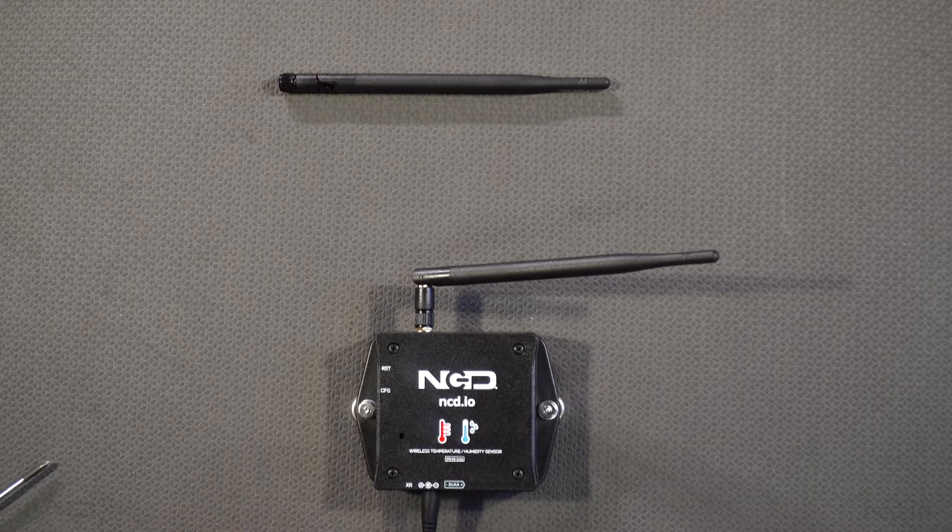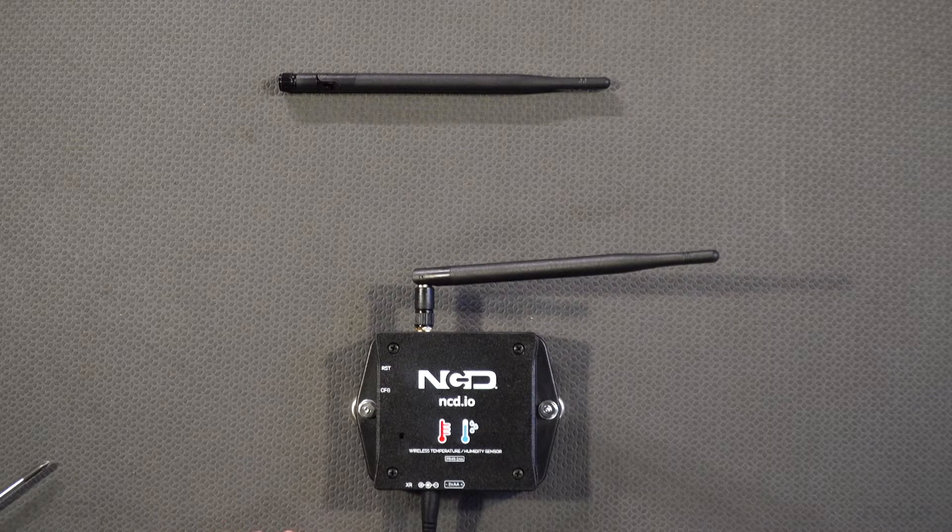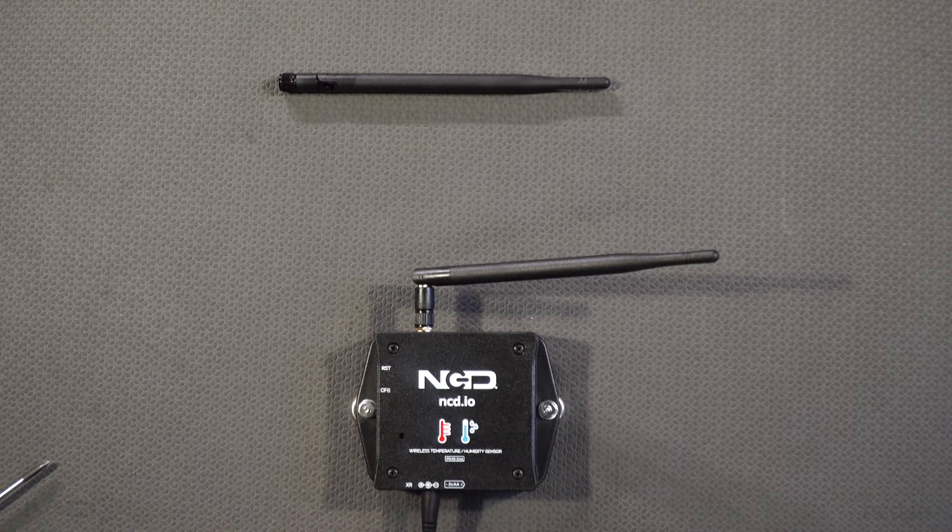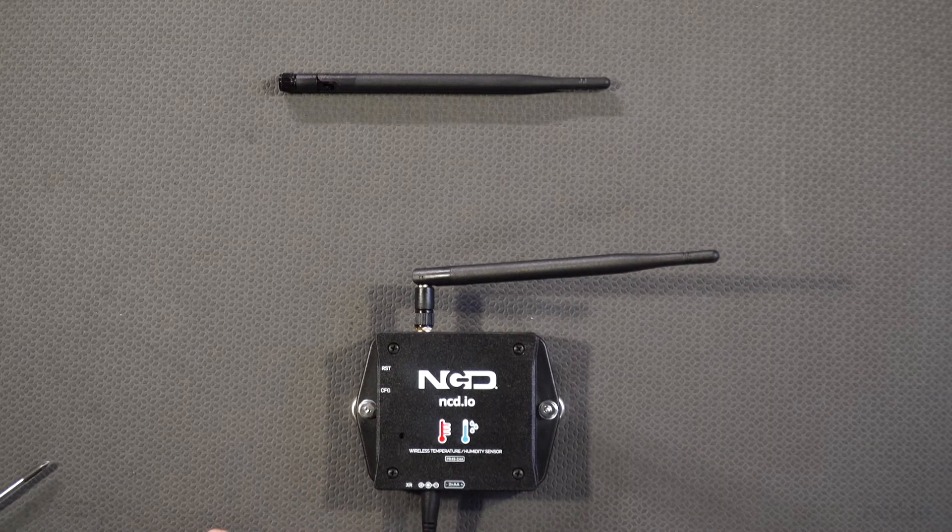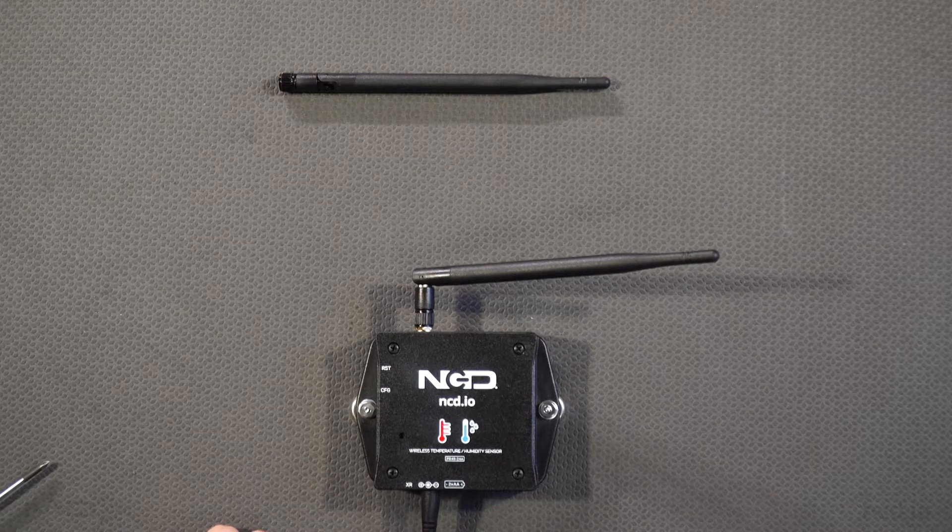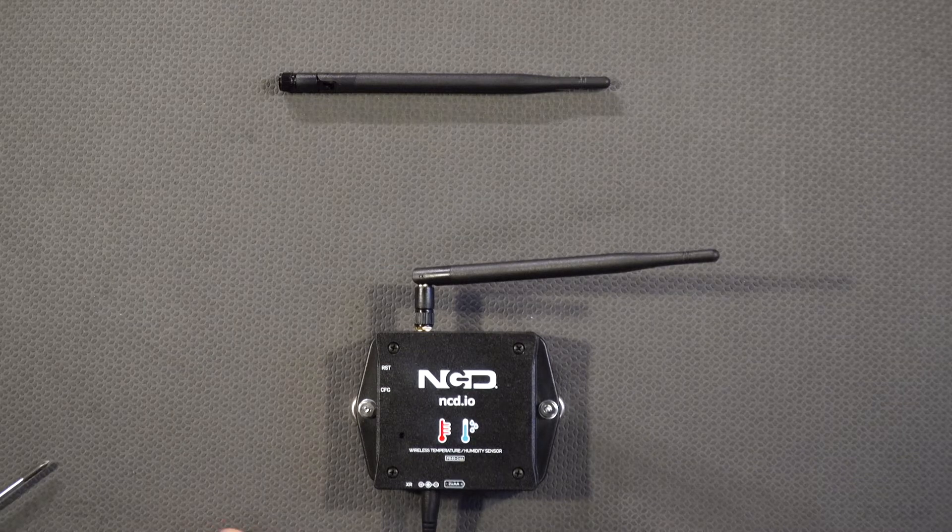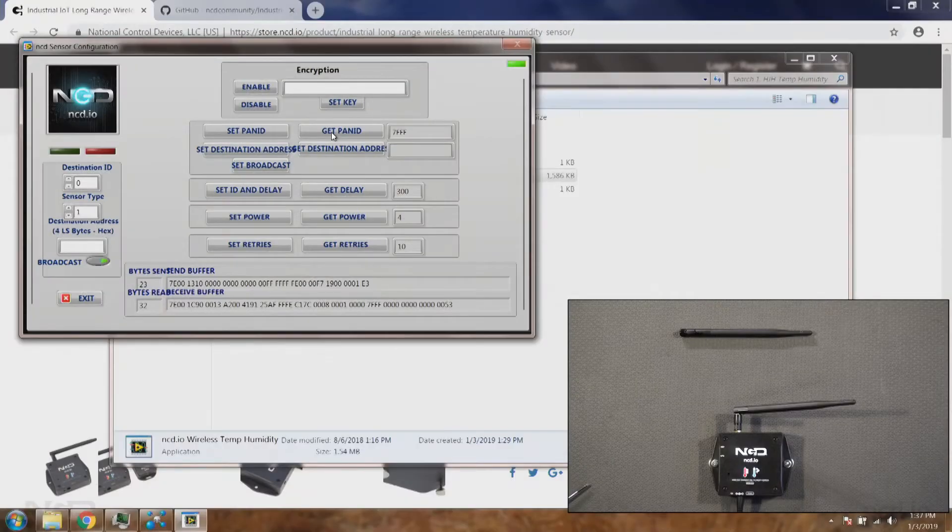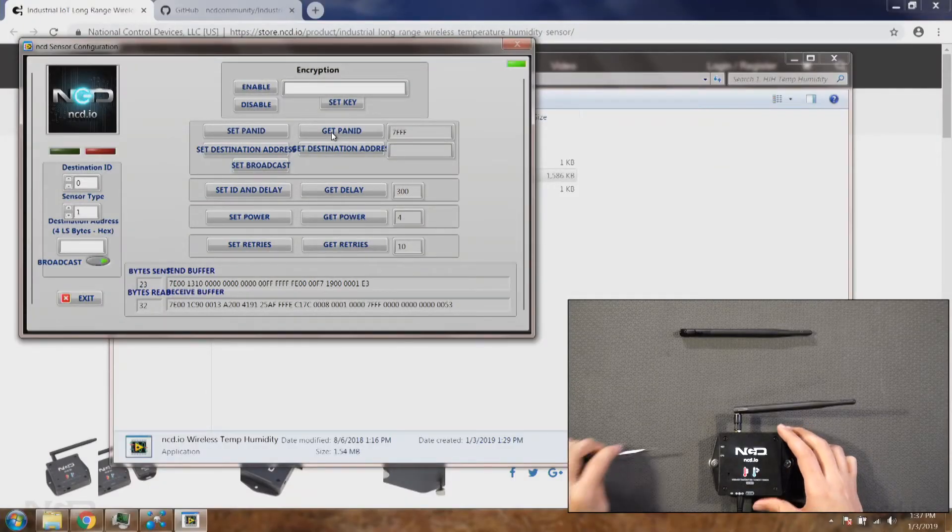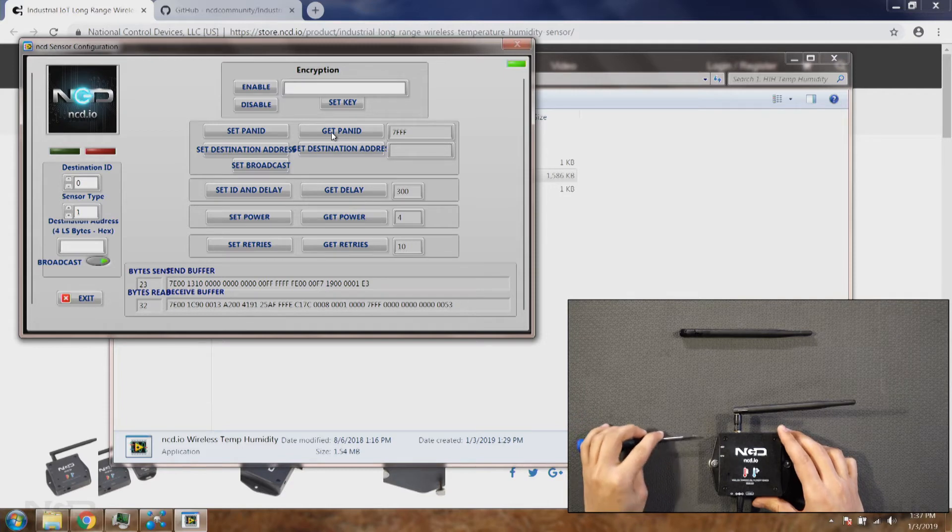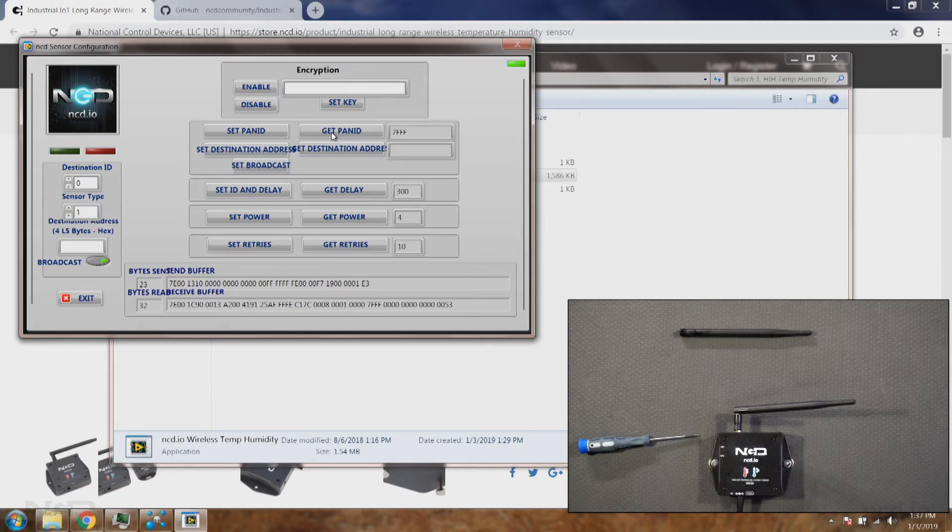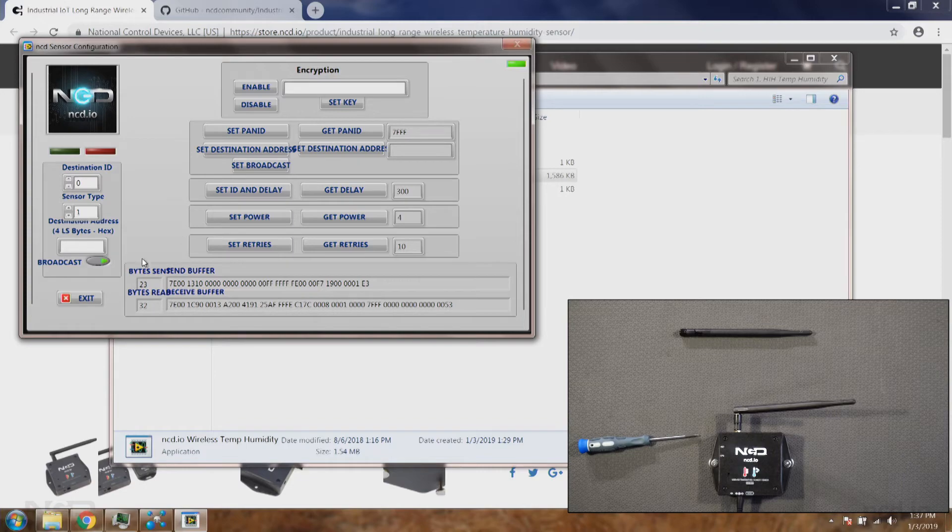One most important thing, once again if you are using batteries during the configuration make sure you don't leave the module in configuration for too long. Once you are done with the configurations, you will hit the reset button and now the sensor will start working as a regular device and it will start sending data after 300 seconds.